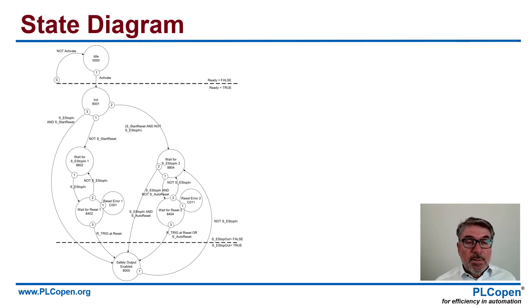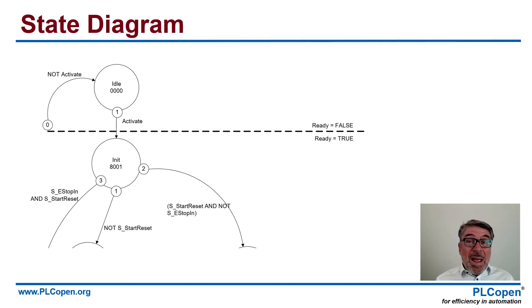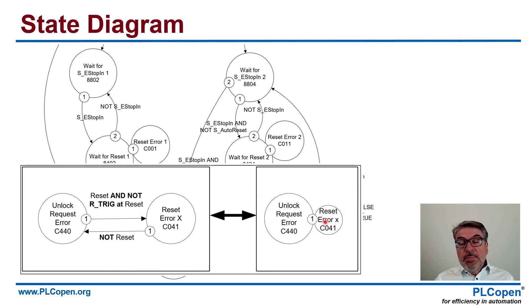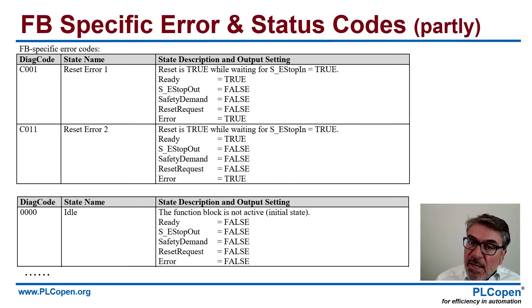We have several timing diagrams per function block. The next one, of course, is the state diagram. This is the whole state diagram for the emergency stop. If we zoom in, we see on top that you put the power on and activate the function block. So you get from ready false to ready true, and you get into the init state 8001. From that one, you have three arrows to go out of it — three possibilities depending on start reset. In the end, you want to go to the bottom: safety output enabled, where e-stop out is true — you are in a safe condition. Then there are the function block specific error and status codes — these are the DiagCodes, this is the state where it is, this is the name of the state, and this is the status of the inputs and outputs.